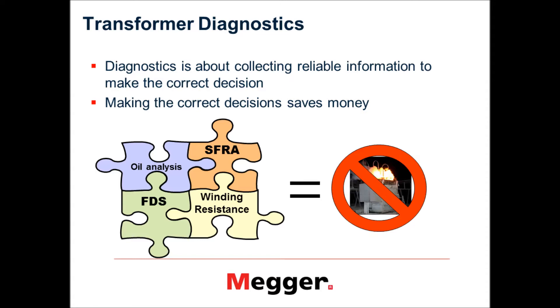But all these tests that we just talked about, none of those tests give me any information about the mechanical condition of the transformer. Has there been any kind of mechanical damage inside the transformer that I am not aware of? What if my windings have shifted? What if my core has shifted or windings have got deformed? None of that kind of information can be picked up by the other electrical tests.